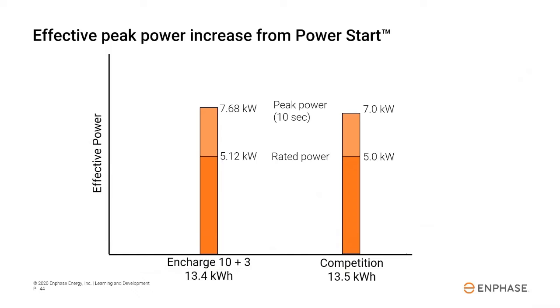How can we quantify the impact of power start on the system's ability to start appliances? Through extensive testing, we've determined that power start effectively increases the peak power output by approximately 30% over the peak power. So here we do a side-by-side comparison. On the left is one Encharge 10 plus a 3, which is a 13.4 kilowatt hour system. And on the right is a 13.5 kilowatt hour system from a competitor. As you can see, the rated power is around the same at 5 kilowatts. The peak power is around 7.5, but the effective peak power of the Encharge system is about 30% higher than that because of the effects of power start.